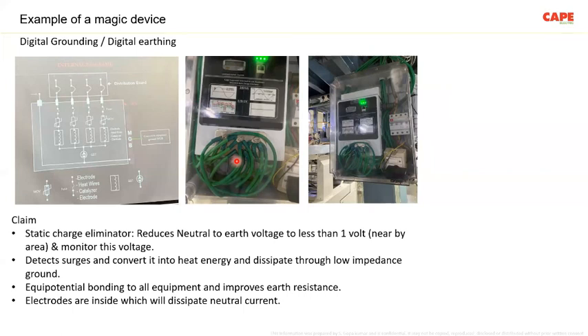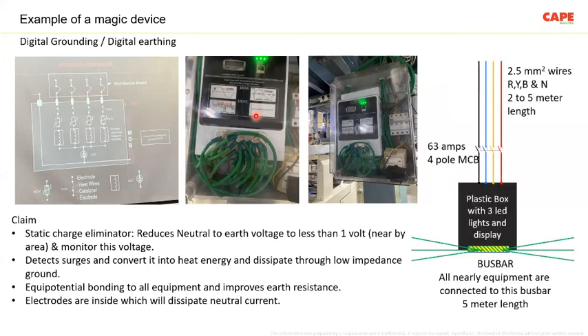Sometimes the words which the manufacturers use are some kind of new words in electrical engineering, which I have never heard of. So basically, this is really a problematic product. If you are using such a product, very soon you will be in trouble. We have experienced in some industrial premises, large corporate companies, that in order to avoid the neutral to earth voltage, this device is used.